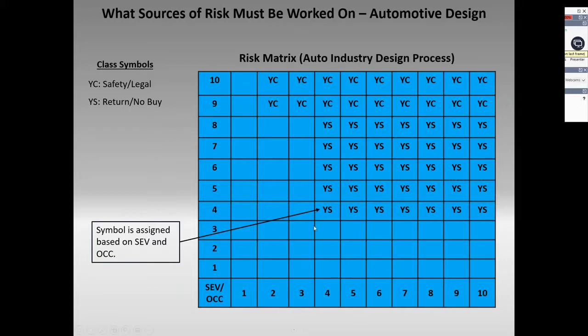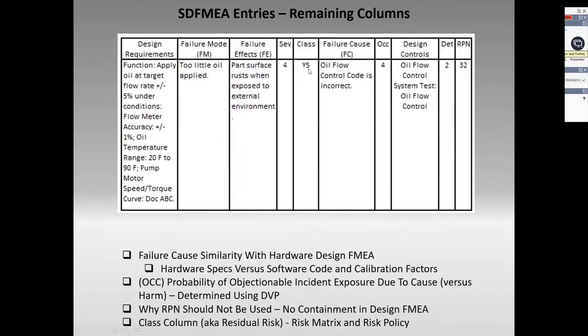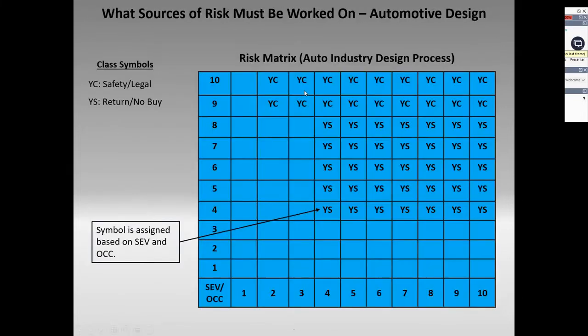Now, what's going to happen is I'll accept some of these, whereas I can't accept others. So there's different thresholds. Bottom line is whenever you do an FMEA, and you take the severity and the occurrence - whether it's a software FMEA, an application FMEA, or a requirement risk assessment - they all have this class column. Any line of these risk documents that has this symbol in it means you must take action, you must have some attempt to fix it. So that's what this is.